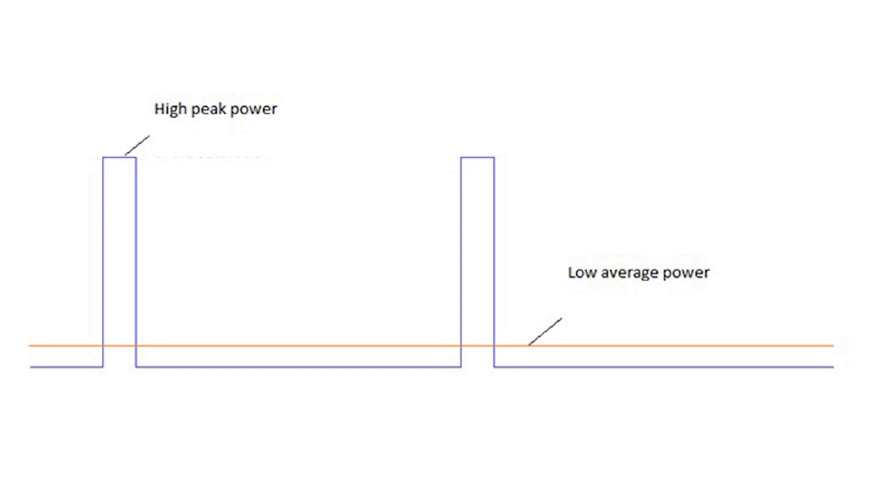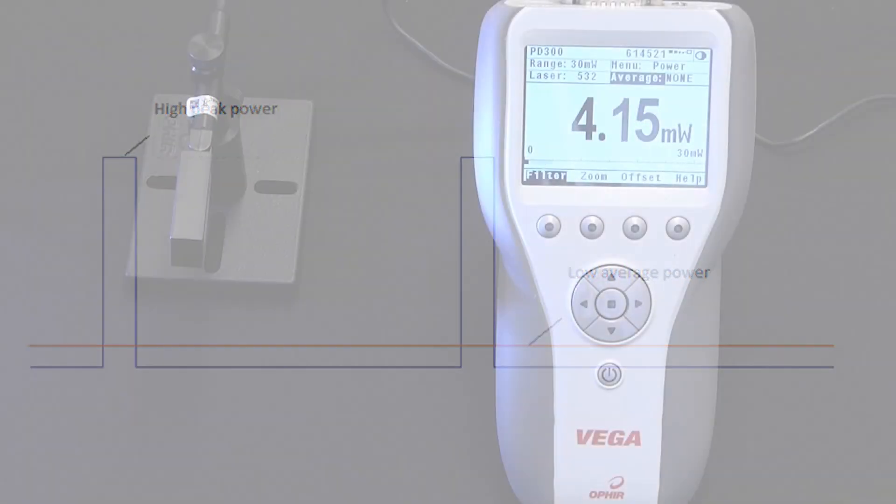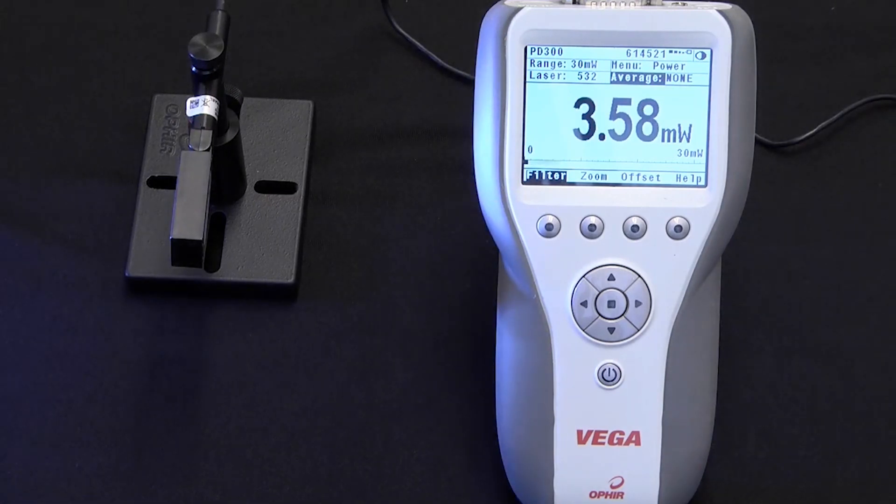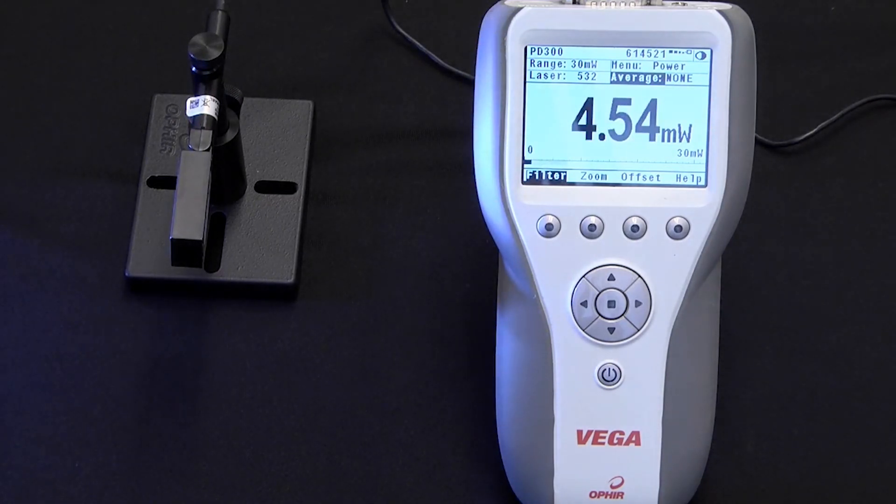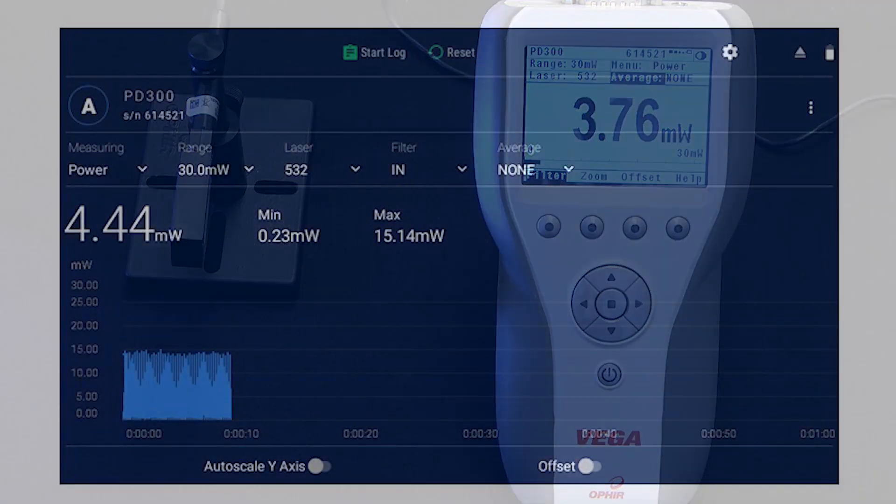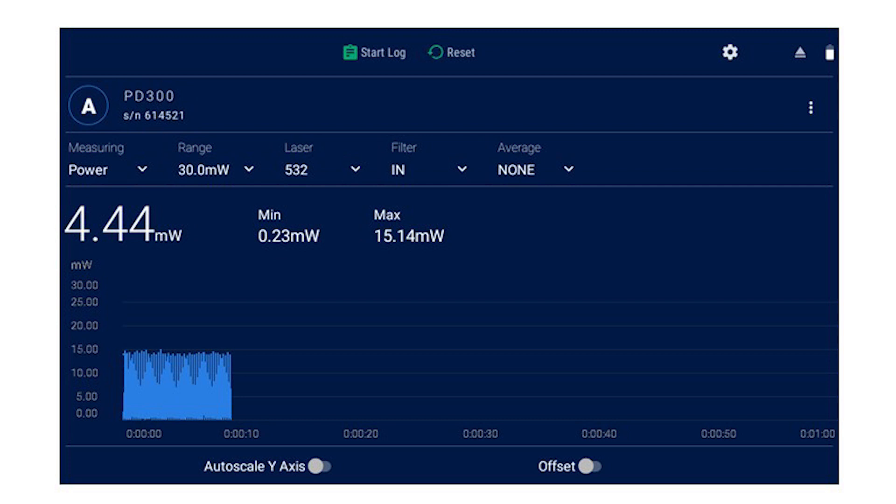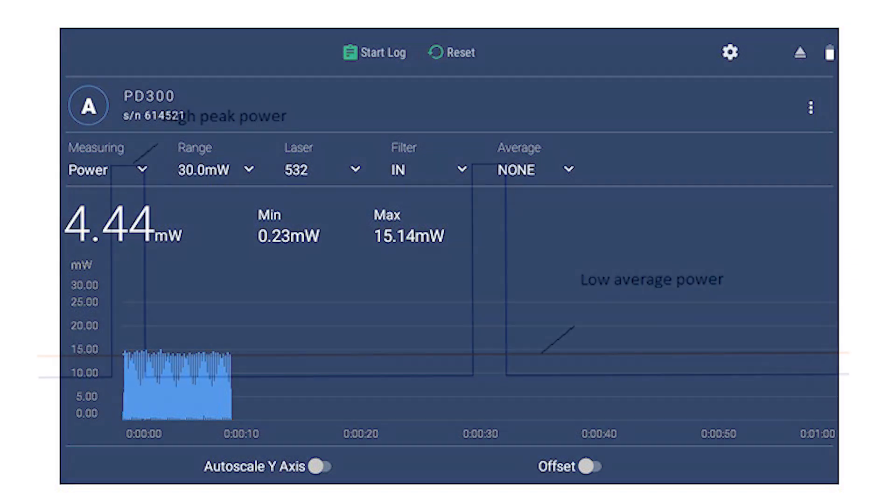Two separate problems result from this. First, the low pulse frequency can beat with the sampling rate typical of laser power meters. For example, a typical Ophir meter samples a power sensor's signal at 15 Hz. If the VCSEL is pulsing at, say, 10 Hz, the readout will suffer from a 5 Hz beat frequency that'll make it very difficult to get a proper reading.